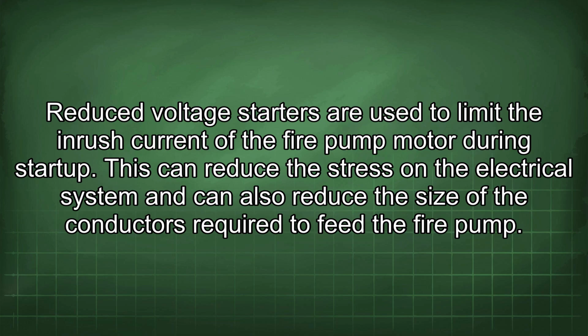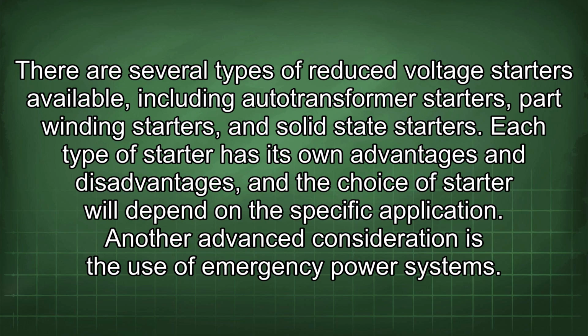feed the fire pump. There are several types of reduced voltage starters available, including auto transformer starters, part winding starters, and solid-state starters. Each type of starter has its own advantages and disadvantages, and the choice of starter will depend on the specific application. Another advanced consideration is the use of emergency power systems.